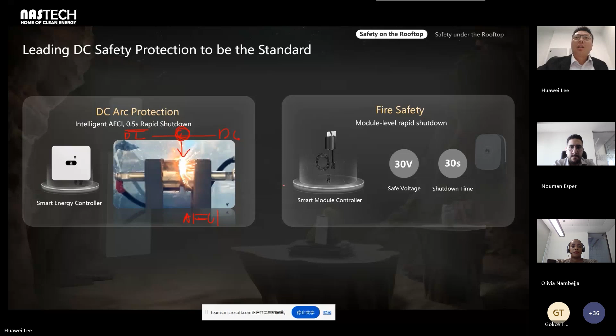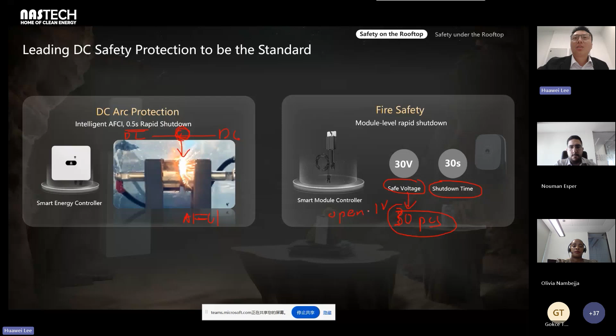And next one is fire safety. We can do rapid shutdown to a safe voltage, with shutdown times within 30 seconds, because we connect a maximum of 30 optimizers, and we can adjust the open voltage to one volt each, so the total is less than 30 volts. Next one is for our residential S1 ES, with some safety protections.